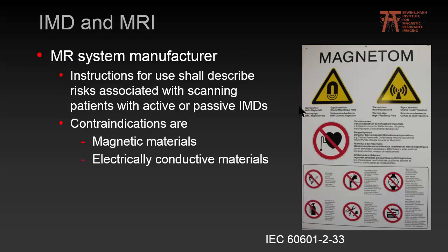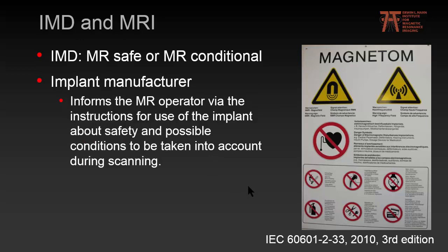Regarding the current situation with implants and the MR system: the IEC standard 60601-2-33 says that the MR system manufacturer shall describe all risks associated with scanning patients with active or passive IMDs in their instructions for use. That's why we have warning signs at our scanner doors. However, in the third edition of the IEC standard in 2010, a statement was included that for MR safe or MR conditional implants, the implant manufacturer should inform the MR operator about safety and conditions for safe imaging — opening a gap that allowed imaging in these patients.